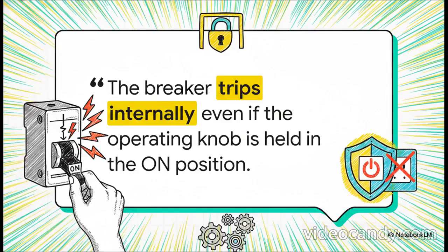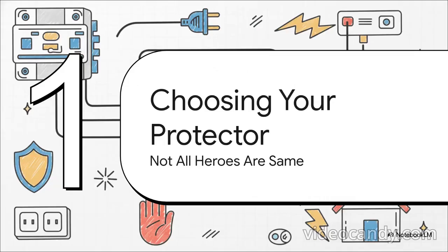Now, this quote highlights a safety feature that is absolutely critical. It's called trip-free. What does that actually mean? It means the internal mechanism works on its own. So even if you were to physically hold the switch in the on position while there's a fault, it will still trip inside and cut the power. You cannot override its safety function, which is exactly what you want.